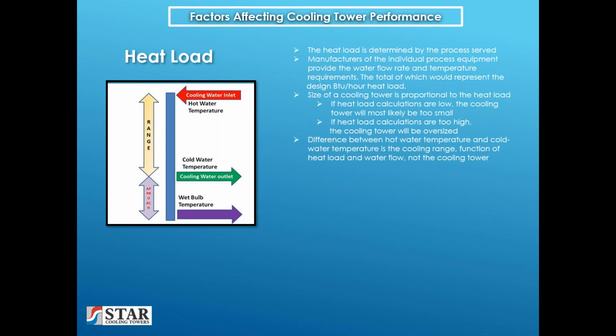If we look at the difference between the hot water temperature and the cold water temperature, we refer to this as the cooling range. The cooling range is a function of the heat load and water flow. A lot of times, the owner-operators take the range as something that the cooling tower provides, but this is no function of the cooling tower. The cooling tower will only provide the cold water temperature. The range is a function of the heat load and water flow. The approach is the difference between the cold water going out and the wet bulb temperature. And typically, average approach would be 5 to 6 degrees to the wet bulb.